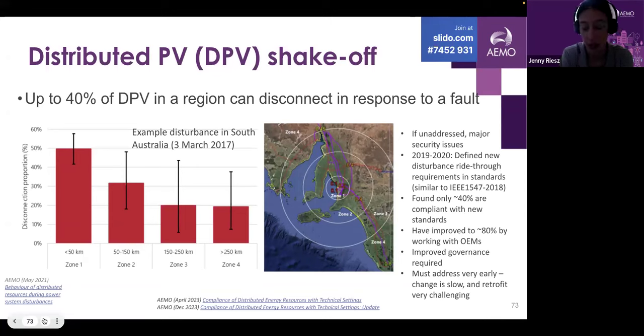There was in South Australia, again, a series of explosions at one of our large gas-fired power stations, which led to voltages dropping very low right in the middle of the main capital, Adelaide, where there is a very large concentration of distributed PV. You can see on the right there where that fault happened on the transmission network, and the minimum voltage recorded was about 0.1 to 0.2 per unit.